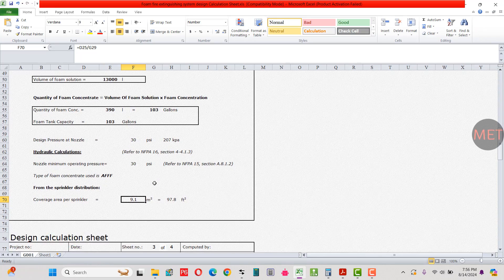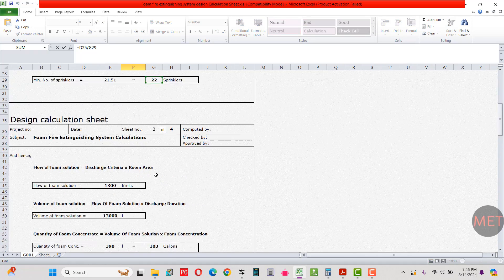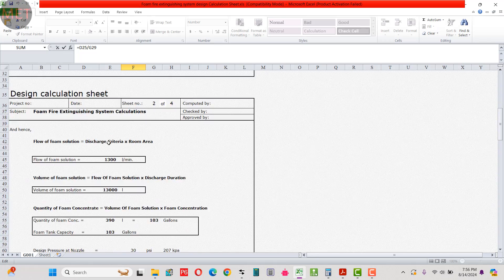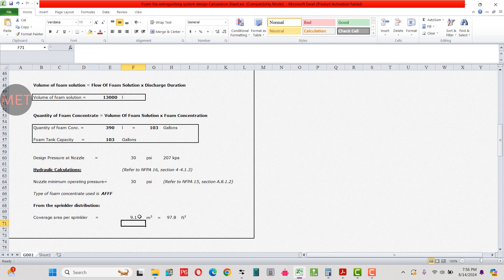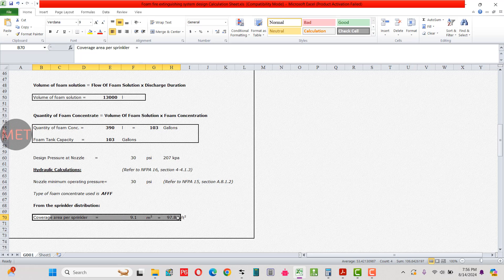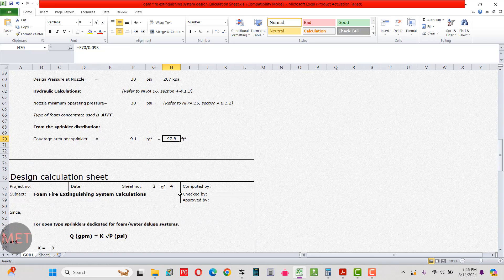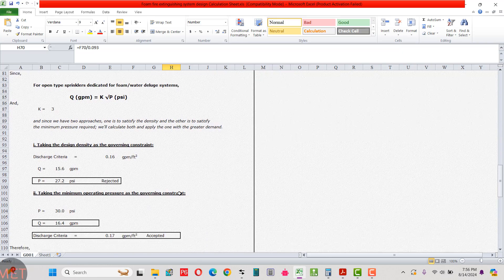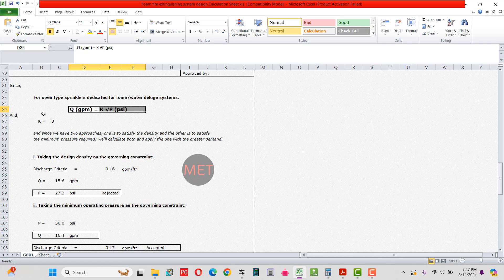For open sprinkler dedicated foam-water deluge systems, the key equation is Q = K√P, where Q is the flow rate in GPM, K is the sprinkler constant factor, and P is the minimum pressure required. The K value must be obtained from the supplier based on the sprinkler used. In this example, K = 3.